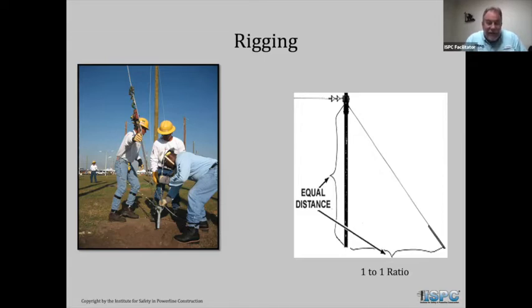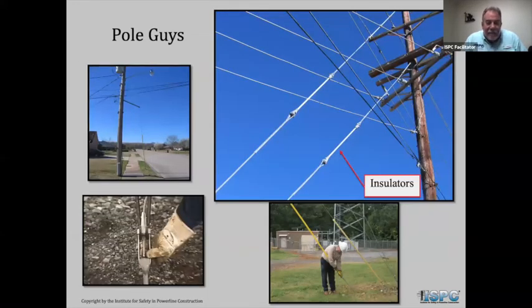So if we have a different voltage between the earth and that guy, then it could be a little bit of a risk. A lot of times our down guys where they're going through the energized conductors will have insulators in them and could be a risk to your guys. If they're also putting a guy and an anchor behind this pole and they actually pull the pole over a little bit, they could possibly sag a conductor and have it sag down into the hazard, causing a risk.